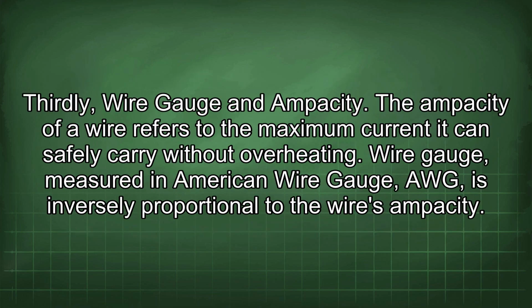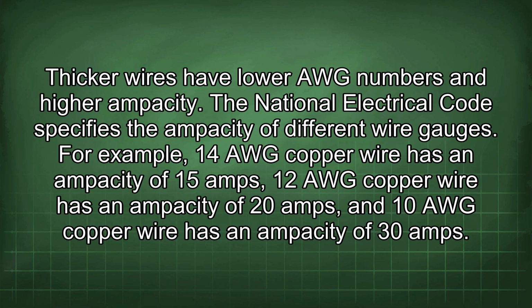Thirdly, wire gauge and ampacity. The ampacity of a wire refers to the maximum current it can safely carry without overheating. Wire gauge, measured in American Wire Gauge, AWG, is inversely proportional to the wire's ampacity. Thicker wires have lower AWG numbers and higher ampacity. The National Electrical Code specifies the ampacity of different wire gauges.